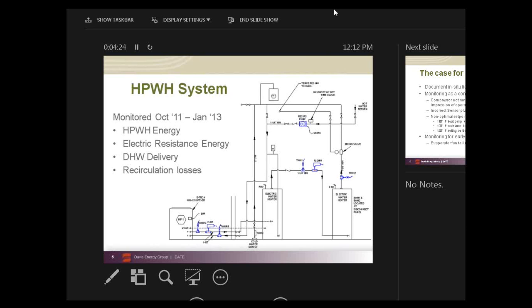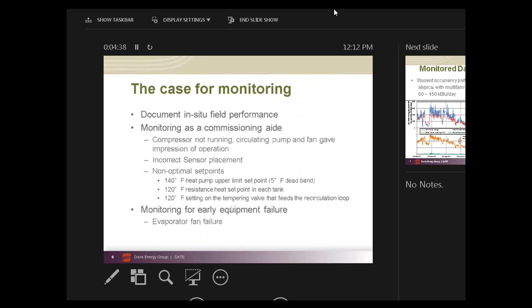Our period of monitoring began in October 2011 and continued until January 2013 so that we could collect at least a full year's data after the initial commissioning phase. So while monitoring was intended for documenting the field performance of the unit, active monitoring became very handy during commissioning. When we installed our sensors and began collecting data, we immediately noticed that the system was not operating properly. The compressor was not running, and all the domestic hot water supply was being delivered by the electric resistance elements.